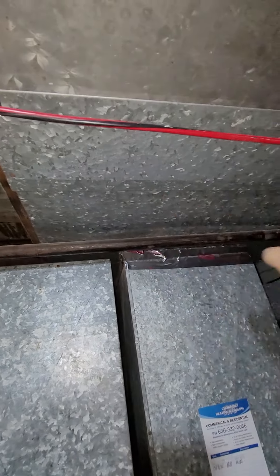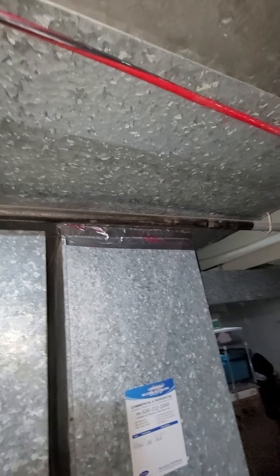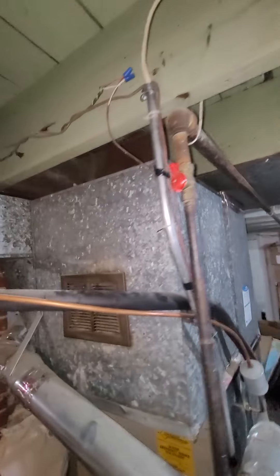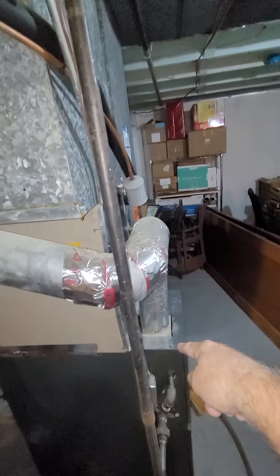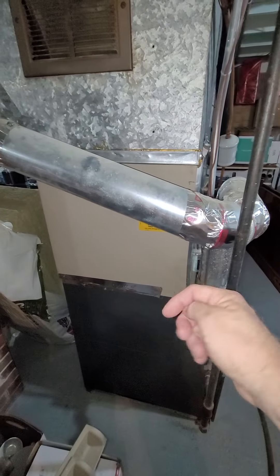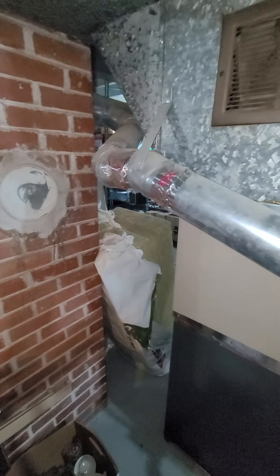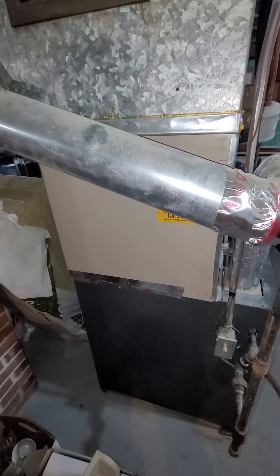So you just turn it sideways and slide it back. It'll bridge these two cavities and pull from both cavities on the return, which just means moving this gas line — or maybe the gas line can come in down on this side. It may have to shorten and come back this way. If you slide it back and face it this way, it should open up space here to where you can slide it right back and hook it into the flue liner back there.